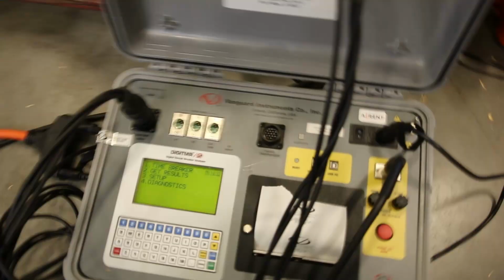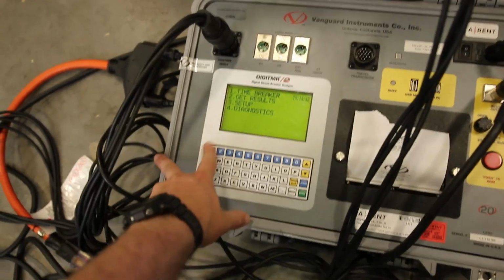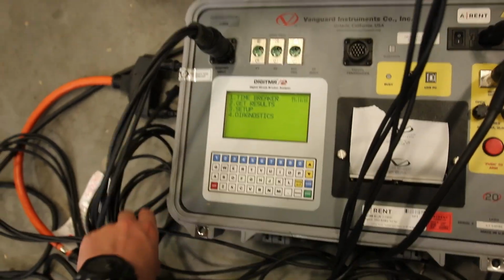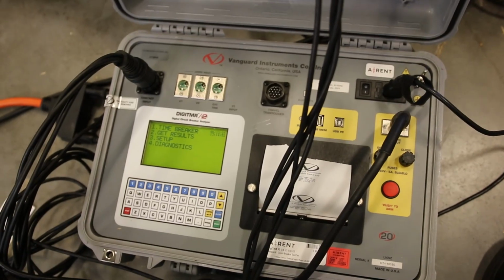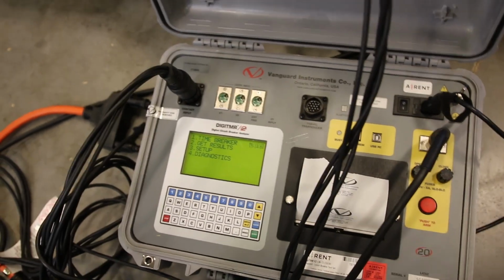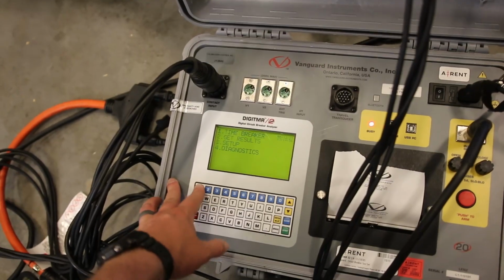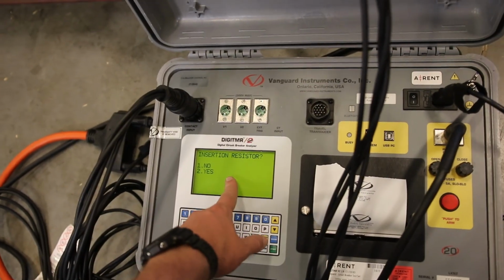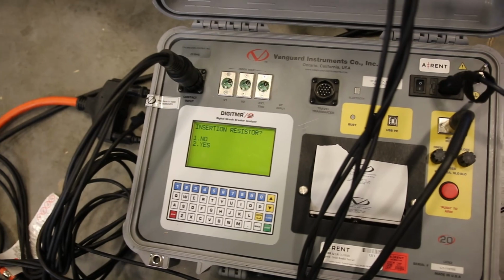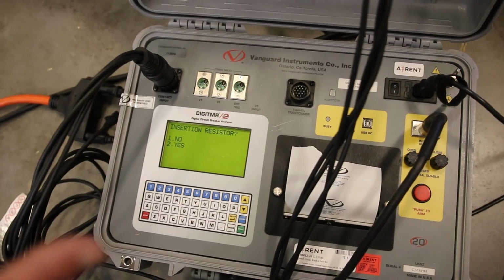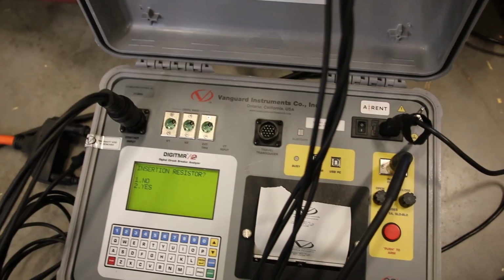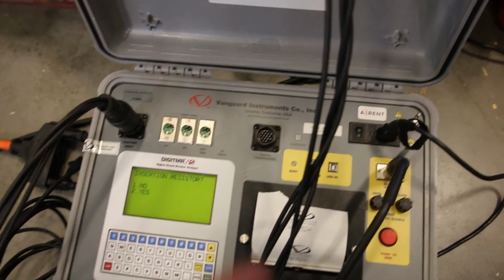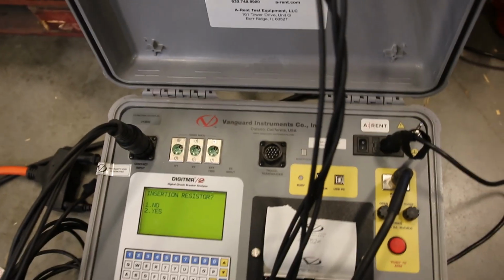I figure this part's not going to be super interesting for you guys unless you know what I'm doing. So on this test set, you can actually run it from your laptop by plugging it in on USB. That works great. We're not going to do that because we're lazy. We're going to go time breaker. Do we have a resistor? There is no resistor needed for this breaker. We're just going to go dry contacts, 120 volts or 125 DC straight into the trip and close motor. So we're going to go no.